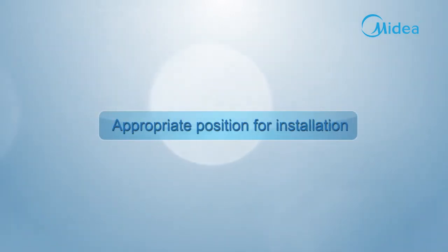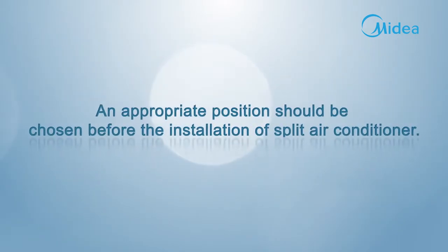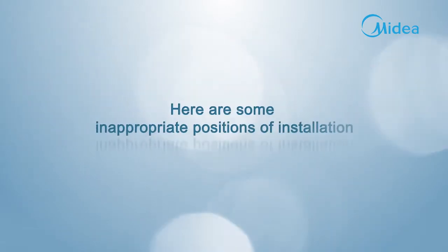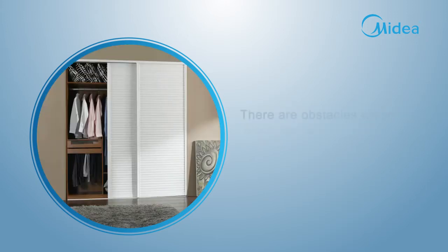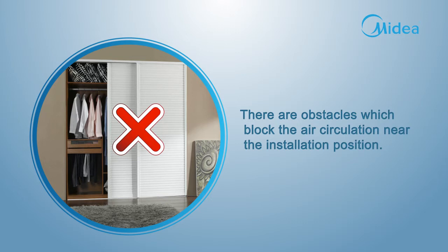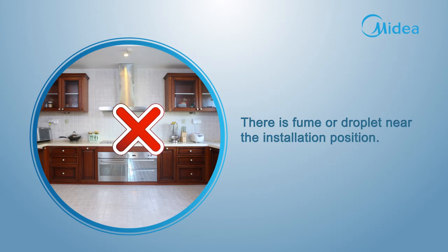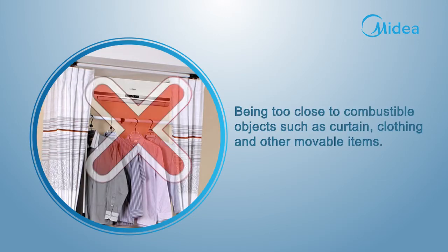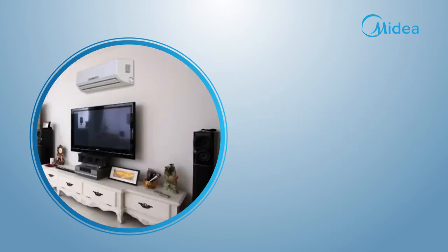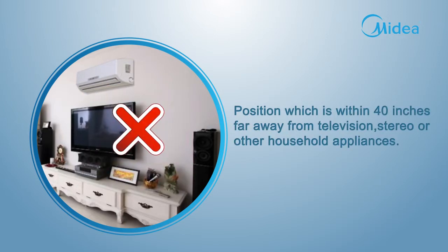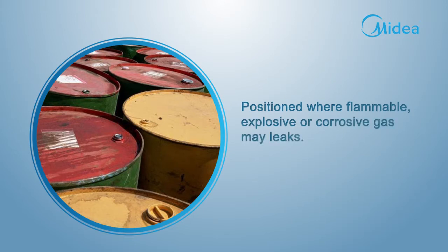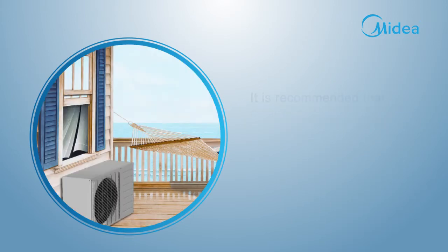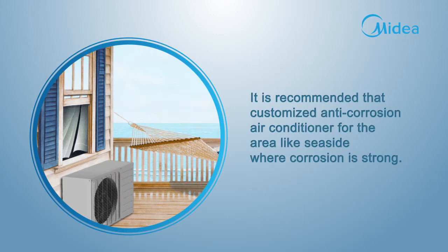Appropriate position for installation. An appropriate position should be chosen before the installation of a split air conditioner. Here are some inappropriate positions: where there is a heat source or steam source nearby; where obstacles block air circulation; where there is fume or droplet nearby; being too close to combustible objects such as curtain, clothing, and other movable items; within 40 inches of a television, stereo, or other household appliances; where ventilation is poor; or where flammable, explosive, or corrosive gas may leak.